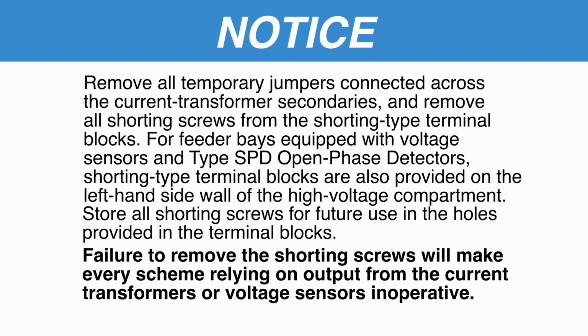Remove all temporary jumpers connected across the current transformer secondaries and remove all shorting screws from the shorting type terminal blocks. For feeder bays equipped with voltage sensors and type SPD open phase detectors, shorting type terminal blocks are also provided on the left-hand side wall of the high voltage compartment. Store all shorting screws for future use in the holes provided in the terminal blocks. Failure to remove the shorting screws will make every scheme relying on output from the current transformers or voltage sensors inoperative.